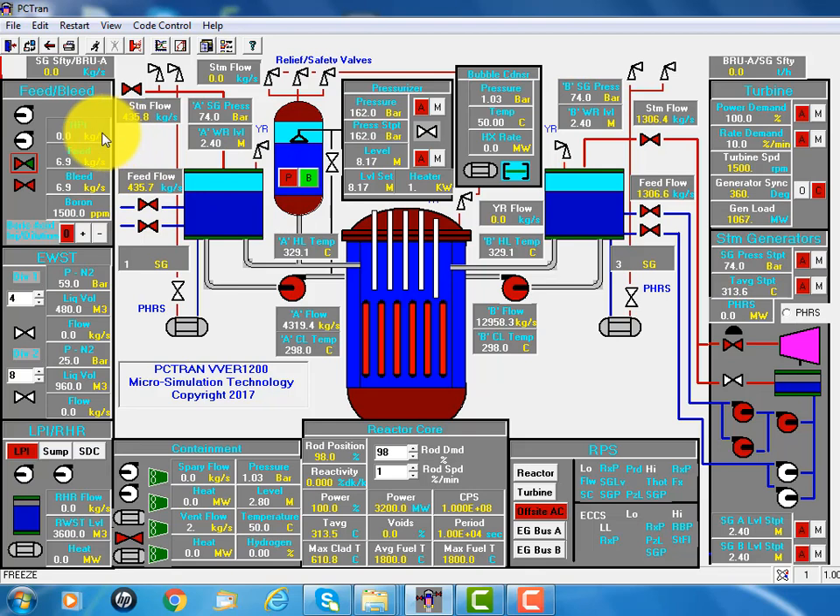For emergency cooling, there are two accumulator systems. In Russian the designation is EWST. The first train — there are four of them — and the nitrogen pressure is built to 59 bar. The second train has eight of them, and their pressure is built to 25 bar.